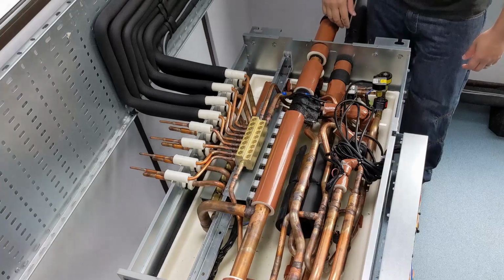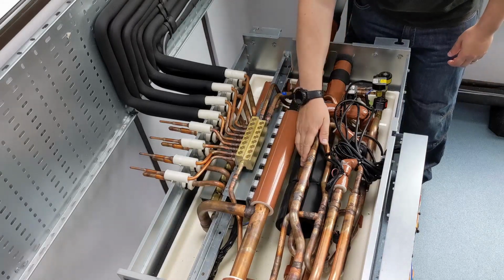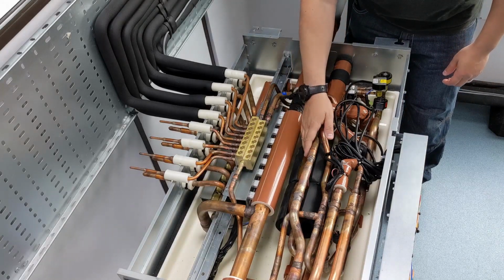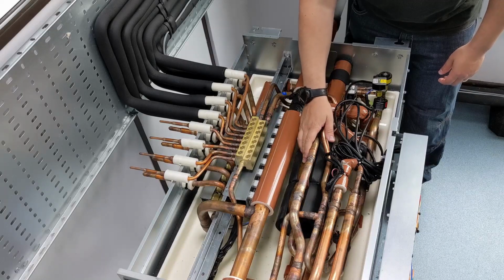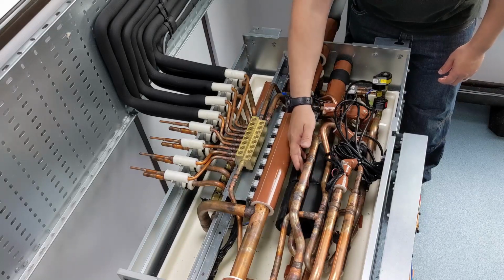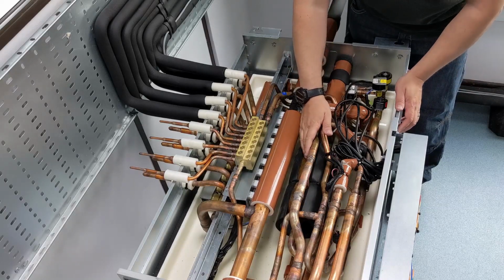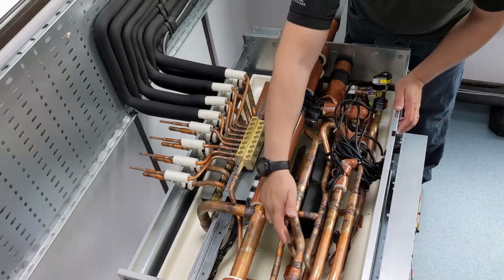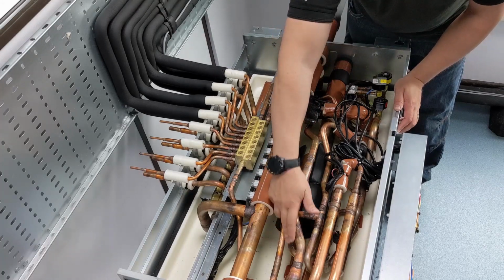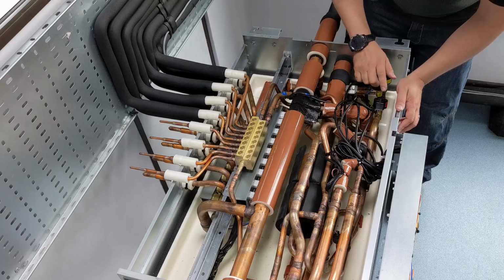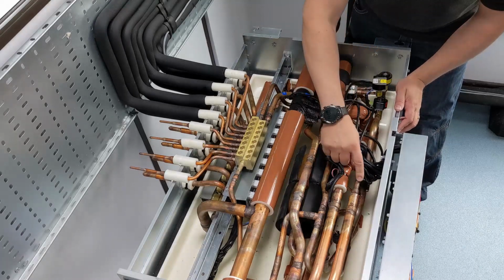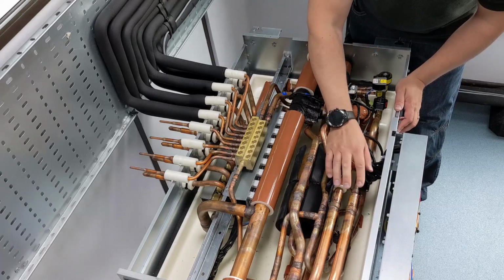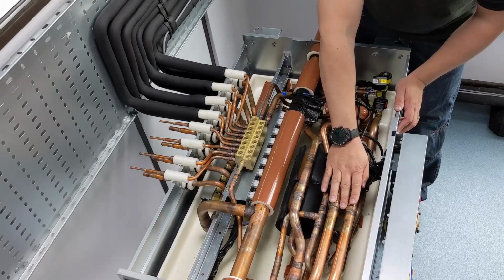As that refrigerant comes into the BC box, it's going to come up to a gas liquid separator. At this moment in time, it's just an empty bit of copper. There's nothing really going on at the moment. We've just got liquid refrigerant passing into there. We're going to draw that liquid refrigerant off the bottom of that gas liquid separator via LEV1, and we're going to pass it into this tube-in-tube heat exchanger. And we're going to use this to subcool that liquid refrigerant.